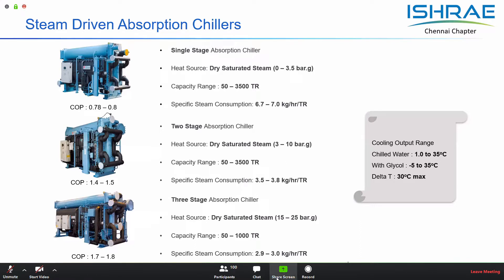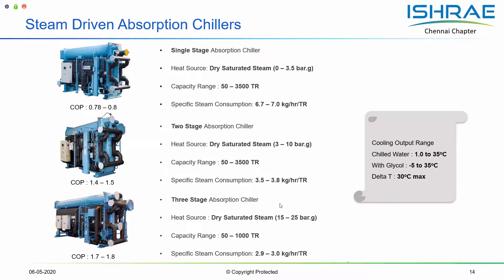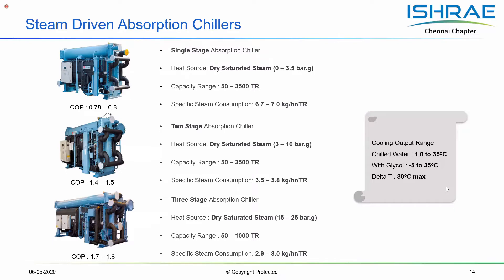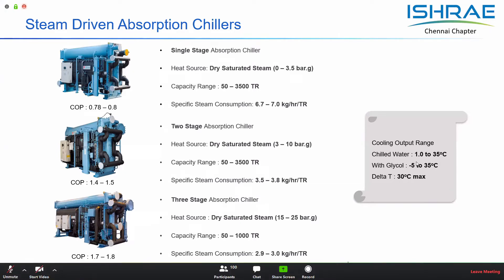When very high steam pressure is available, we can go for a three-stage absorption chiller, where steam consumption is less than 3 kilograms per hour per USRT. The output possible from an absorption unit with this heat source includes chilled water down to 1 degree Celsius of pure water, or if glycol solutions are used, down to minus 5 degrees Celsius using conventional lithium bromide absorption technology.